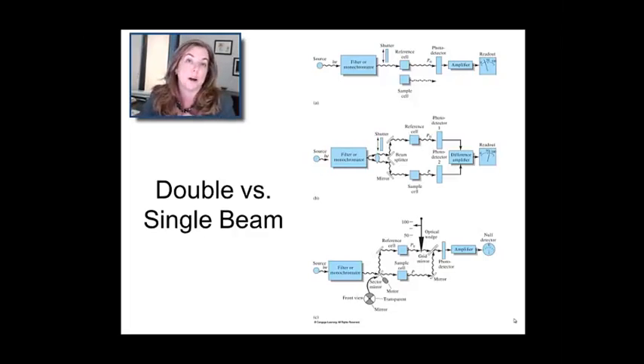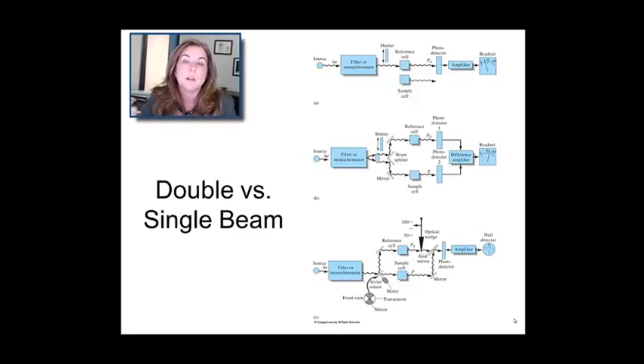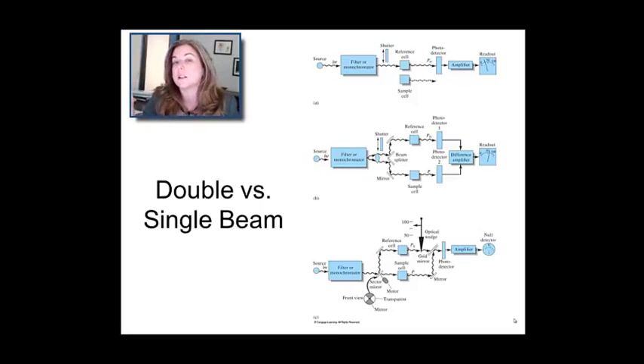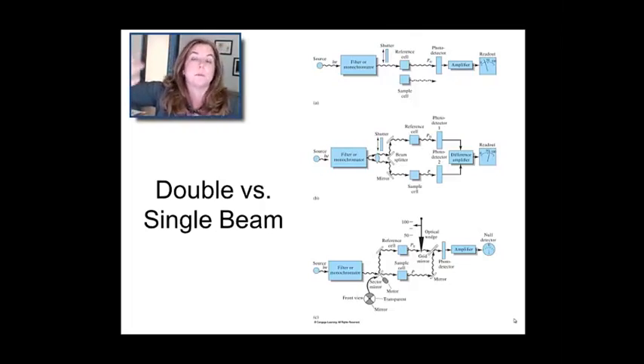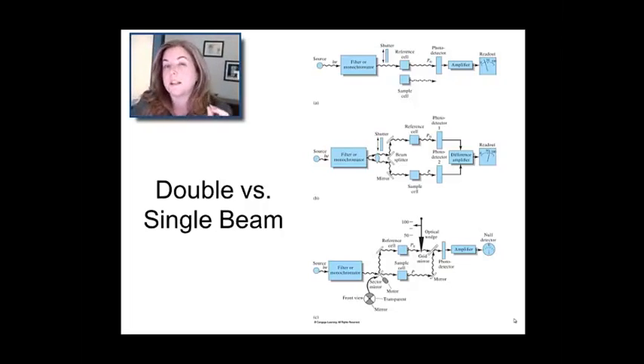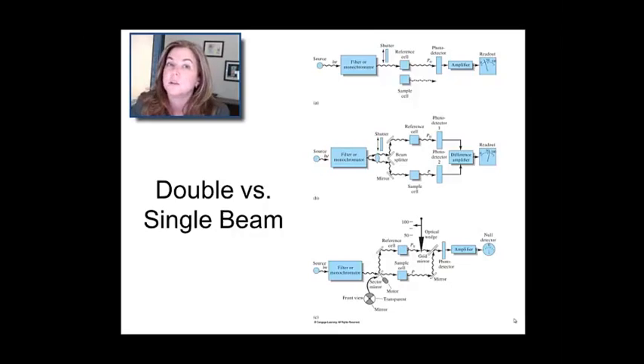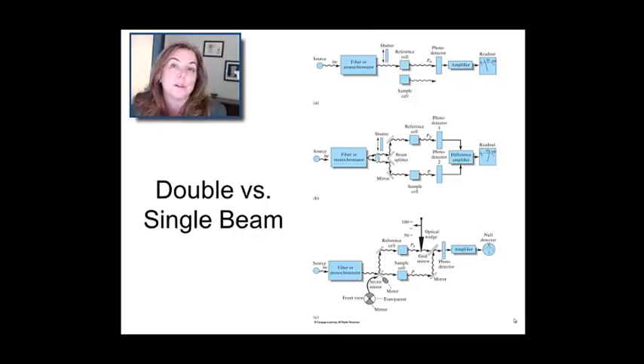Most spectrometers are double beam spectrometers that simultaneously measure the sample and the blank. If you don't have enough money for that, you can also use a single beam where you alternate: sample, blank, sample, blank. But be aware there's a big difference — double beam spectrometers have much less noise and much more quantitative Beer's Law performance for figuring out how much material you have in a liquid sample, for example.